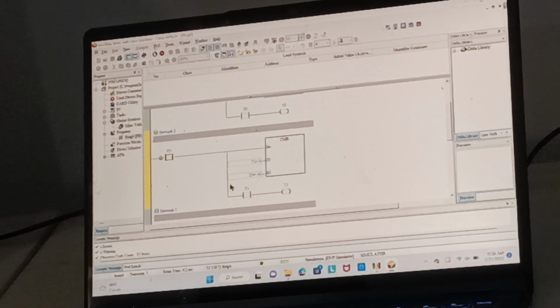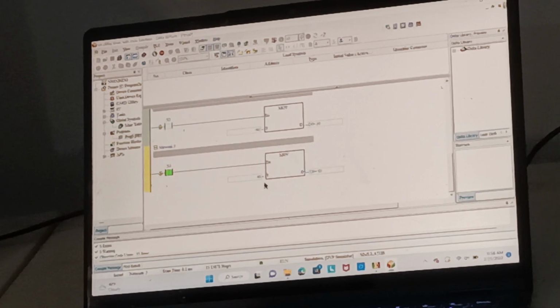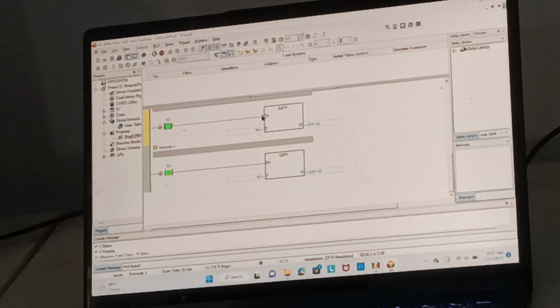So, one other thing. What if I were to push them all on at the same time? This is really why you want to have a momentary on-off, because if you had a toggle on or off, you could have multiple of these move functions being triggered at the same time. Say we turn on our 6 second one. Well, my D0 is 6 seconds, but if we forget it's on and we try to move our value to 4 seconds with this still being on, well, shoot, it doesn't move because it just goes with the highest value.